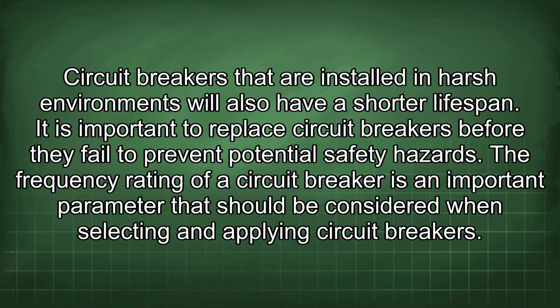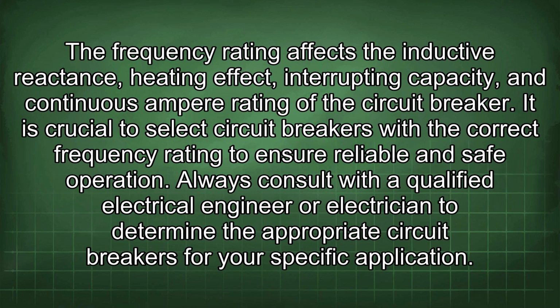The frequency rating of a circuit breaker is an important parameter that should be considered when selecting and applying circuit breakers. The frequency rating affects the inductive reactance, heat effect, interrupting capacity, and continuous ampere rating of the circuit breaker. It is crucial to select circuit breakers with a correct frequency rating to ensure reliable and safe operation.